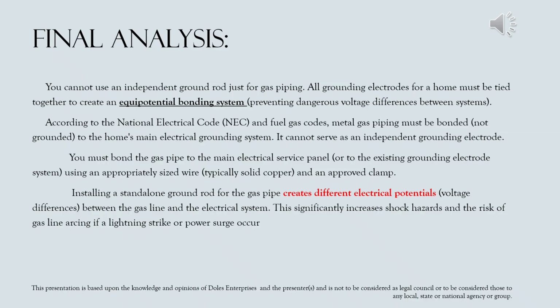Installing a standalone ground rod for the gas piping actually creates different electrical potentials between the gas line and the electrical system. This could increase shock hazards and also the risk of the gas line arcing if a lightning strike or a power surge should occur.